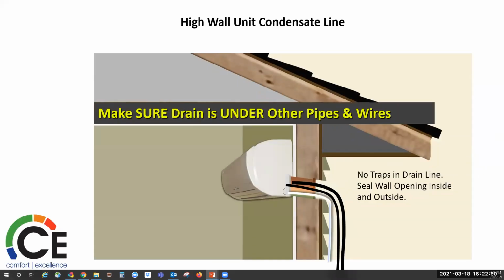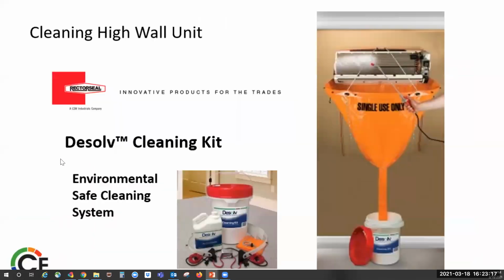Drain lines. This particular photo or picture is set up for the gravity condensate. You don't want to pinch it. You want it as low as possible. You don't want to give it a trap. Obviously, you want to seal the hole, put the electrical wires, whole line set on top of it, just as long as you're not pinching it. And then cleaning. It is a good idea to get one of these cleaning kits so you don't make a mess all over the homeowner's house.